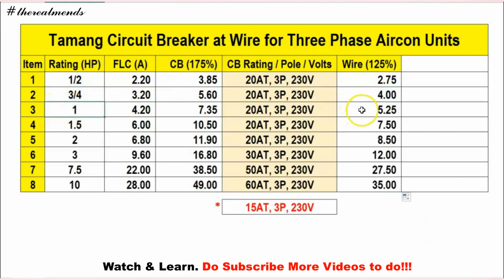For 1, 5.25. For 1.5, 7.5 amperes. Okay, so on sa 10 HP, meron tayong 35 amperes. And then, after that, i-check natin yung available wire size together with yung kanyang ampacity base sa PEC.